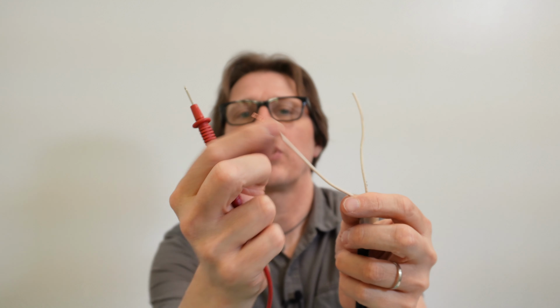We want to trace the wire all the way back to where it plugs into the control board, since it may be broken somewhere in that pathway. So let me use a dirty example here. I'm going to stick the probe in, with one end on this connection and the other at the exposed copper end. If I touch this, I have tone.